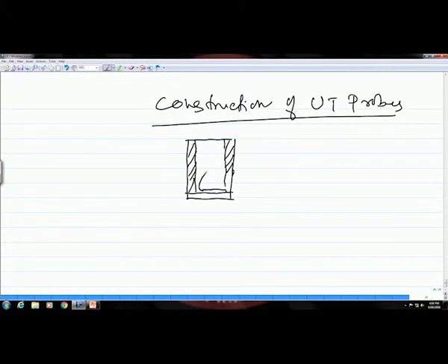To which you have two electrical leads connected like this to supply that electrical signal, and then you have this inner sleeve and other things to house it properly in place. And here at the front face you have some protection for wear and tear. So, you have what is called a wear shoe, and this is the active element.